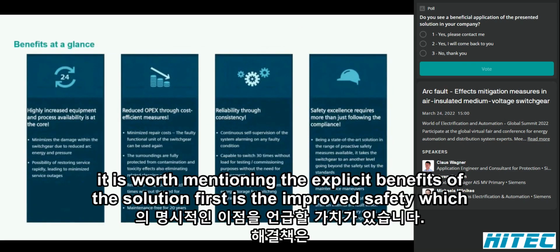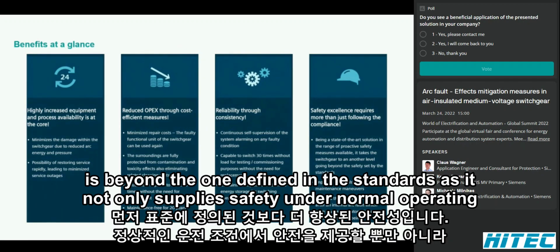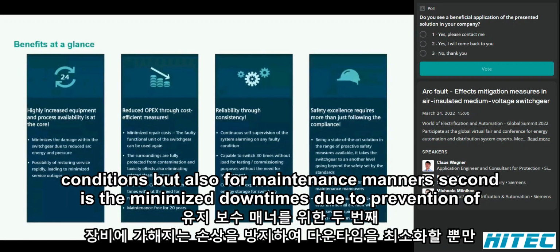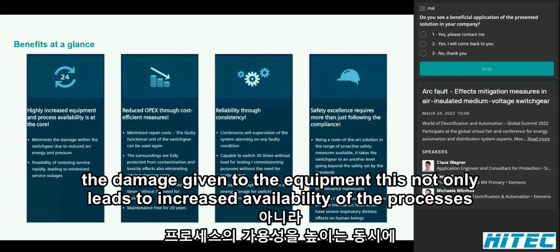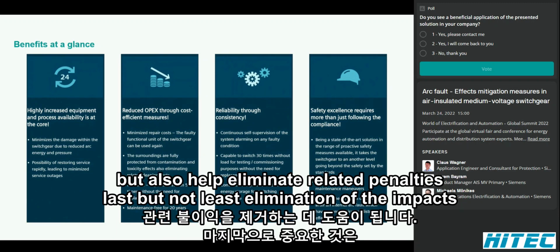It is worth mentioning the explicit benefits of the solution. First is the improved safety, which is beyond the one defined in the standards, as it not only supplies safety under normal operating conditions, but also for maintenance maneuvers. Second is the minimized downtimes due to prevention of the damage given to the equipment. This not only leads to increased availability of the processes, but also helps eliminate related penalties.